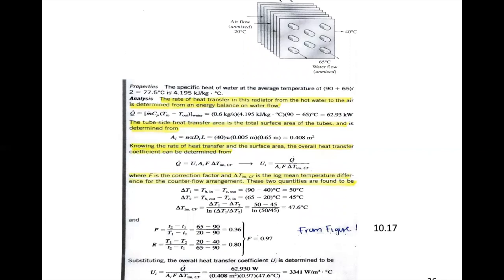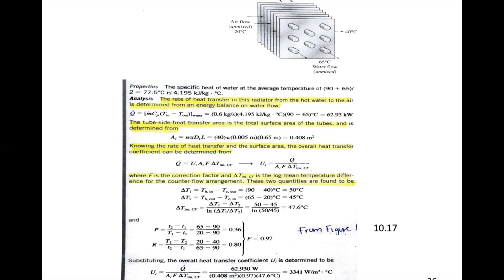Now we have everything: ΔT_lm, correction factor F = 0.97, area A_i, and heat transfer rate Q. We calculate the overall heat transfer coefficient based on the inner area: U_i = Q / (A_i · F · ΔT_lm) = 3341 W/m²·°C. As a note, the overall heat transfer coefficient on the outer side will be much lower due to the large surface area on that side, but we are adding fins to compensate. That concludes the LMTD method.